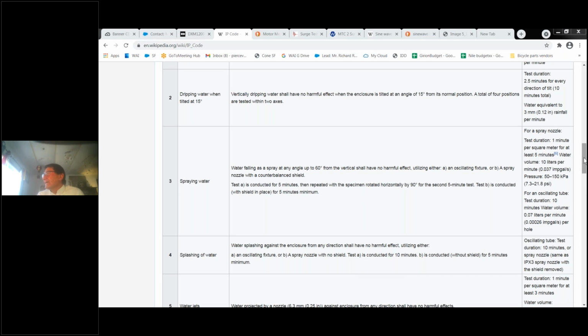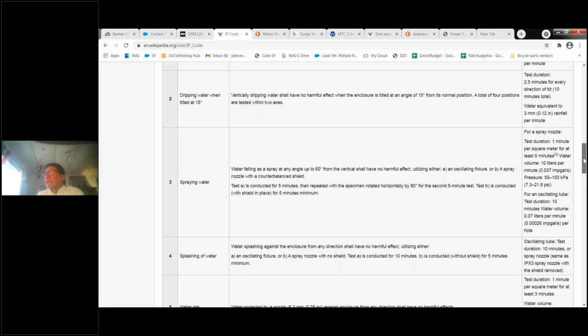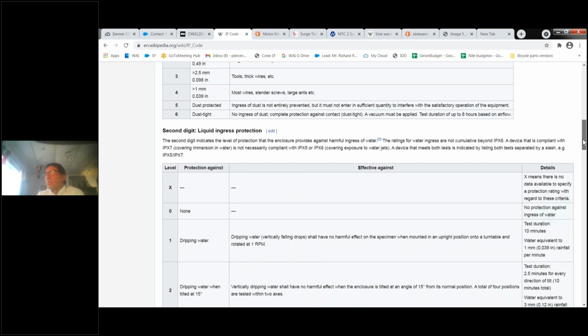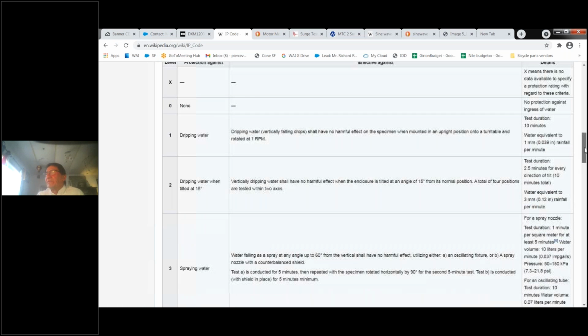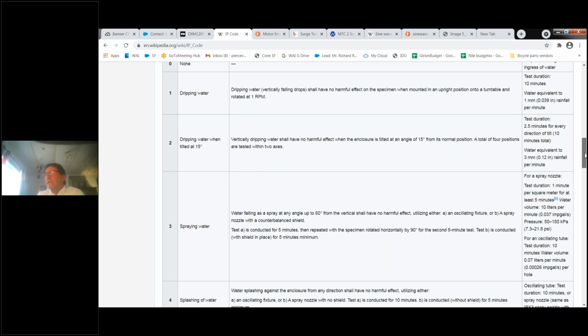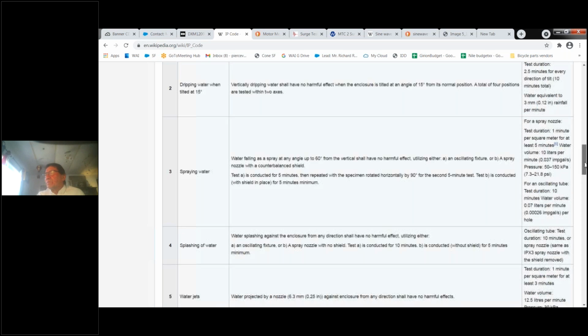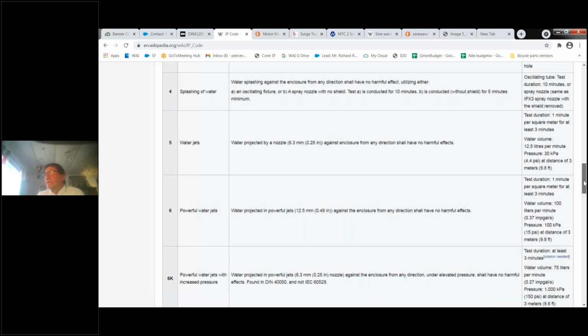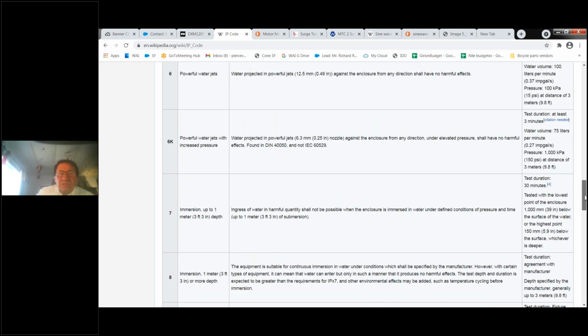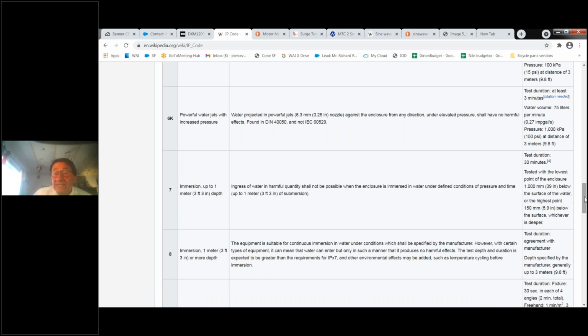So now we're talking about the second number in the IP rating, and that is our liquid level protection. Again, 0 is none. 1 is dripping water. 2 is dripping water when tilted at 15 degrees, which is kind of the NEMA 3R standard. Spraying water, splashing water, water jets, powerful water jets, right on up to 7, which is that device that I talked about was IP67, so no dust ingress, and 7 meaning you can dunk it into water up to 3 feet 3 inches.